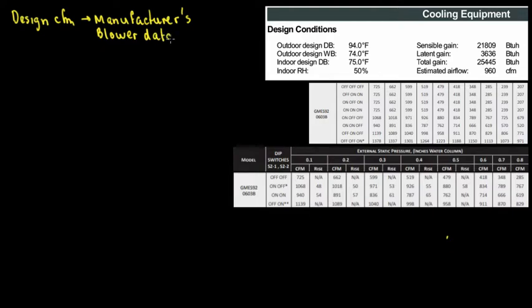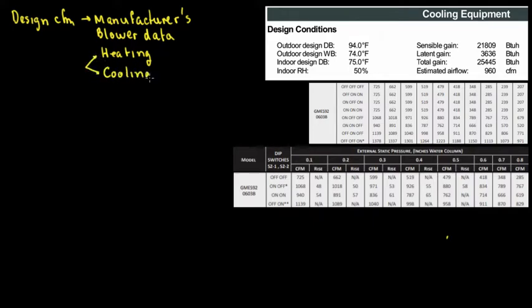If you want to obtain the data from the manufacturer, you need the model number of your furnace. After doing a Manual J and Manual S, you can go to the next step. We are prepping for Manual D, which is duct design. The manufacturer's blower data gives you two sets: heating data and cooling data.